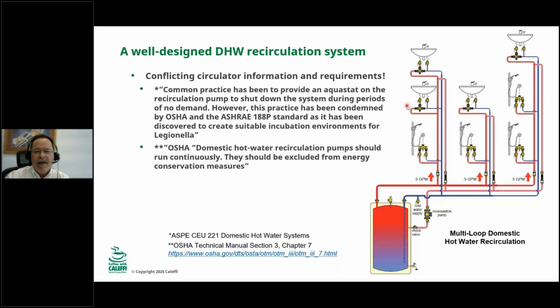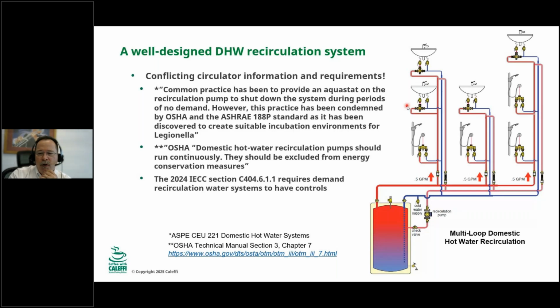On the other hand, you have some other references. This one I found says that there should be demand controls on the recirculator. And we know that in some areas like California, the energy codes say you have to put an aquastat or some kind of a time clock on them. So there's two camps. I believe that we should just run these all the time because today's smart pumps are very, very efficient. The energy that a smart pump will consume is almost negligible in terms of the total energy that you're using to heat this water. So that's my opinion. Probably some people disagree with that, but that's where I'm at.